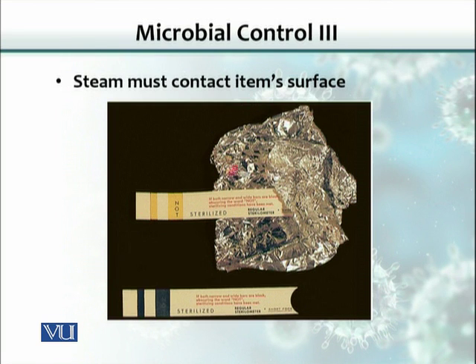It is very important that during autoclaving you should not use aluminum foil, though many people in the lab use it to cover objects. Aluminum foil does not allow steam to penetrate, and steam penetration is critical for achieving sterilization. Instead, you can use simple paper, parchment paper, or a porous plastic wrap.